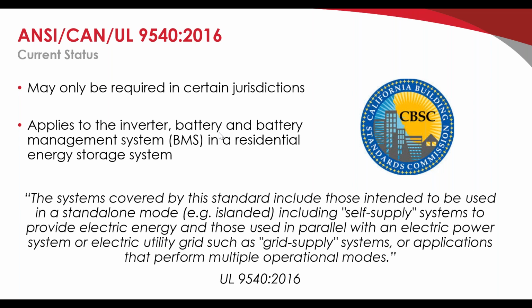However, with other battery chemistries, which will be available for UL 9540, the battery and the battery enclosure will need to be tested together. So from the code itself, the systems covered by the standard include those intended to be used in standalone mode, islanded, including self-supply systems to provide electric energy, and those used in parallel with an electric power system or utility grid, such as grid supply.